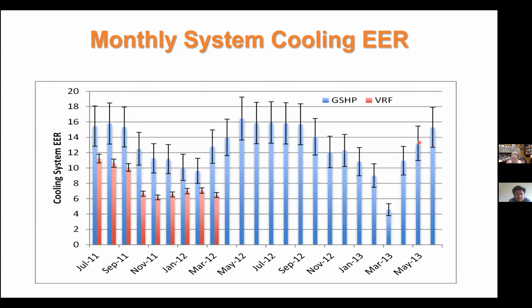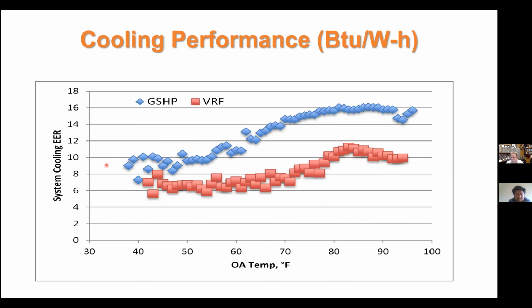Okay, so if we also show the EER, and this is in American units of BTUs per hour per watt, that's why these values are so high. If you want it on a dimensionless basis, you'd have to divide by 3.4. The ground source heat pump system is quite a bit higher than the VRF system from month to month. And there are reasons for that. Some of them are simply related to the source temperatures, and also it probably doesn't appear the equipment's quite as efficient as expected.